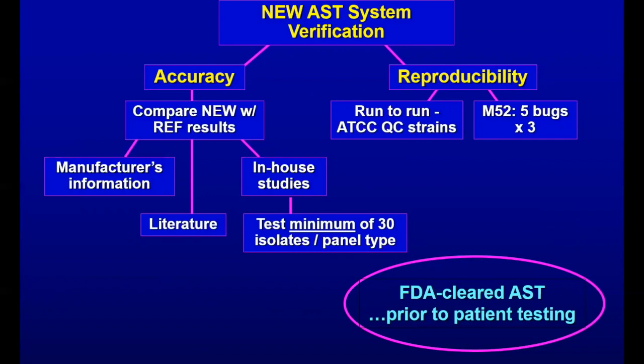And if this is a system that's been out for some time, it's also imperative for us to look at the literature to see if any others have reported any concerns with this new system you're going to introduce to your laboratory. So this can give you some insight into how to develop your verification so that any limitations, any problems with that system can be analyzed during your verification. And then we're going to do some in-house studies.